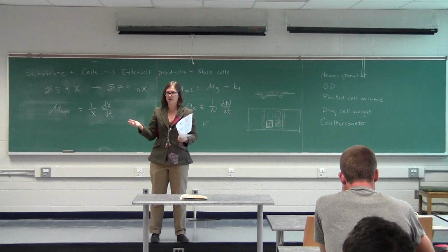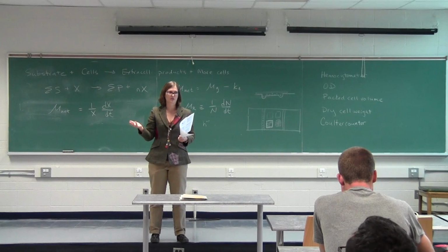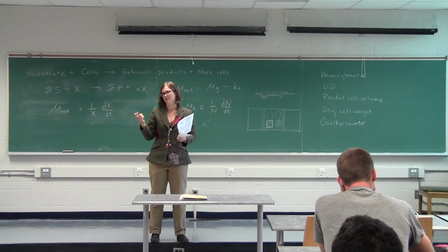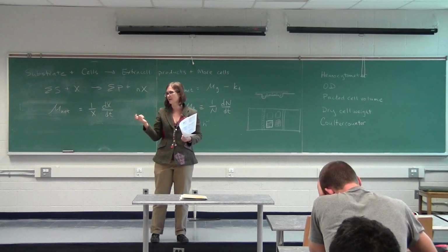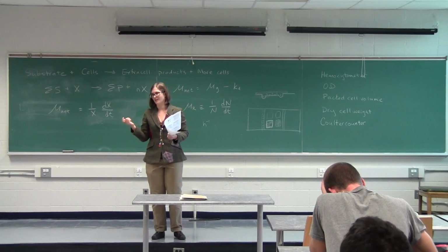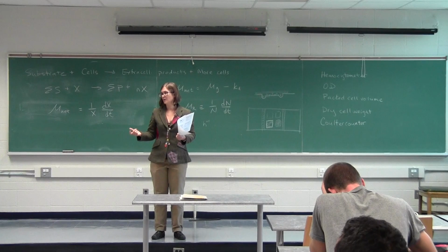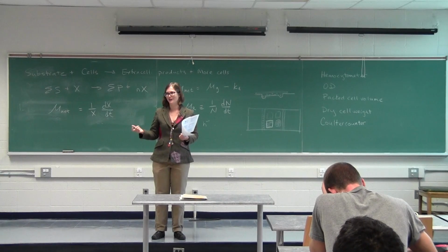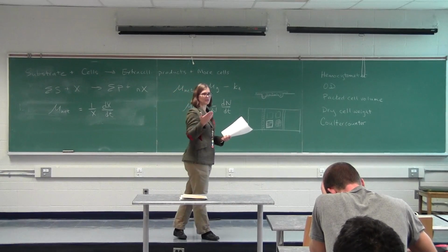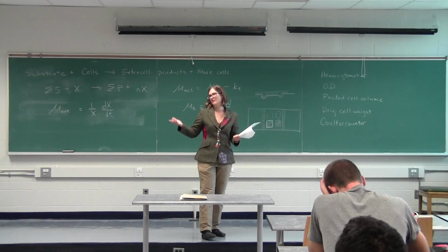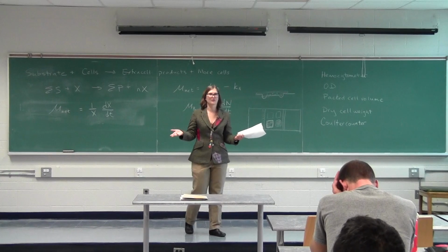Again, typical Coulter counters won't tell you the difference between live and dead cells, because the impedance is about the same between a live and dead cell. There are fancy Coulter counters that can do some optical staining checks at the same time, which you can spend more money on. It'll do it very rapidly for you, much the same way as a flow cytometer will really tell you a lot about whether the cell is alive or dead, or lots of other things about the cells.